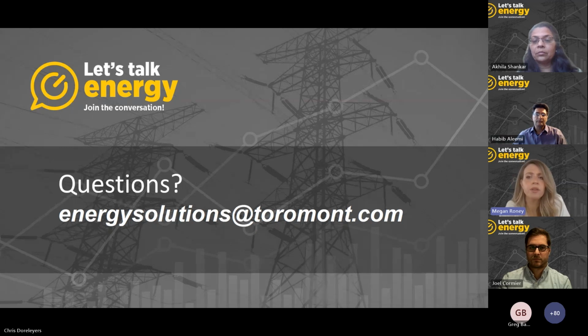Is there an opportunity to utilize what you're proposing in a UPS droop-like solution? The droop solution provides an energy efficient solution. It would also provide cleaner power to the facility with the double conversion. The droop system can also replace all the battery-backed static UPS equipment required to support the critical IT loads and the standby diesel generating equipment required for continuous power supply. So does anyone have an answer for that? No, we'll have to get back on that one. Okay, so we'll get back to you on that one.